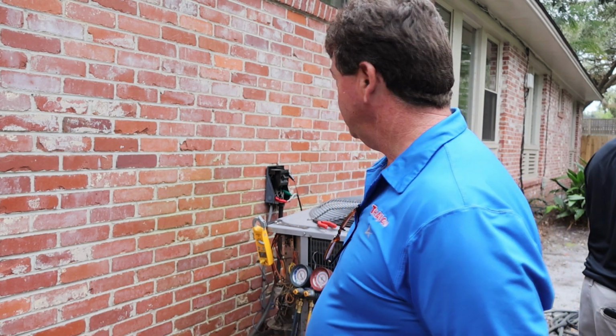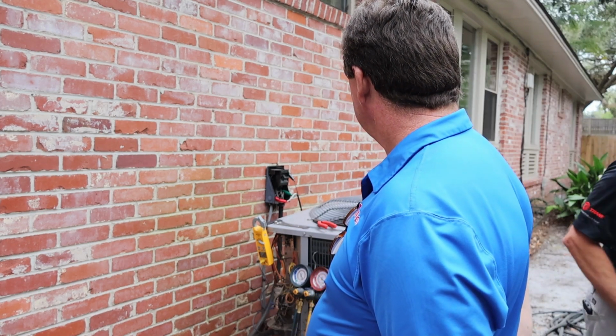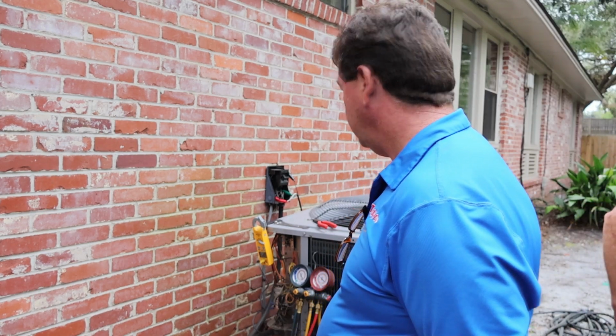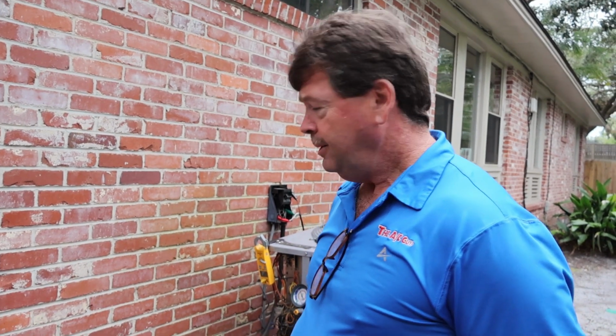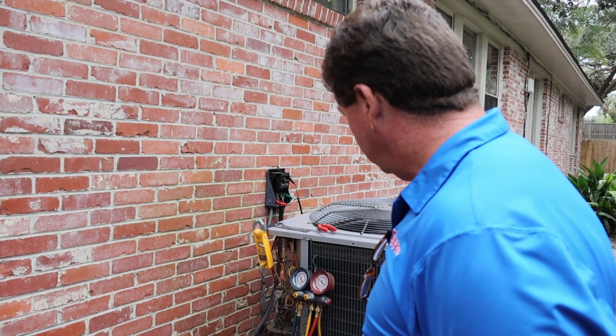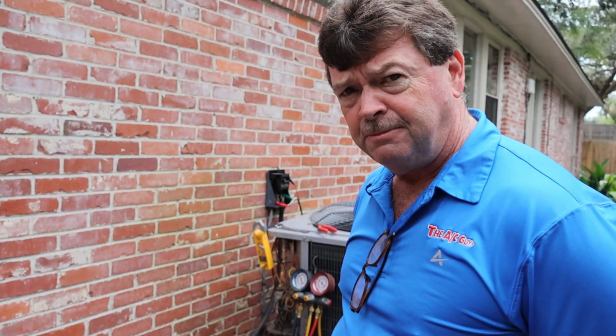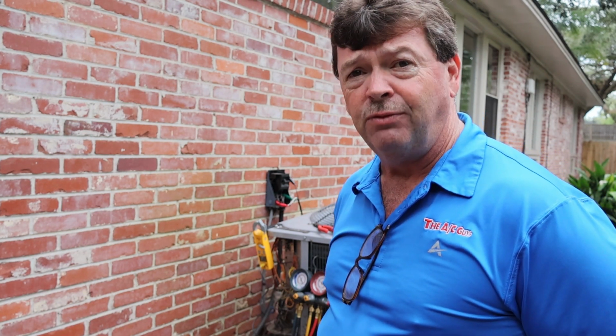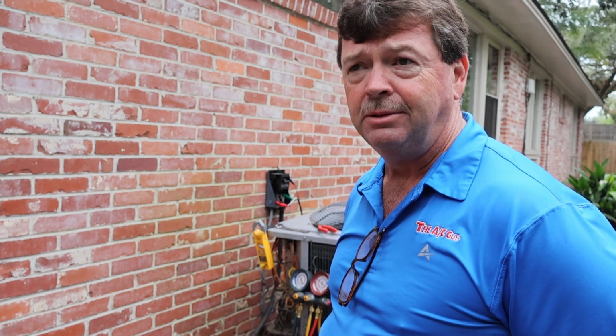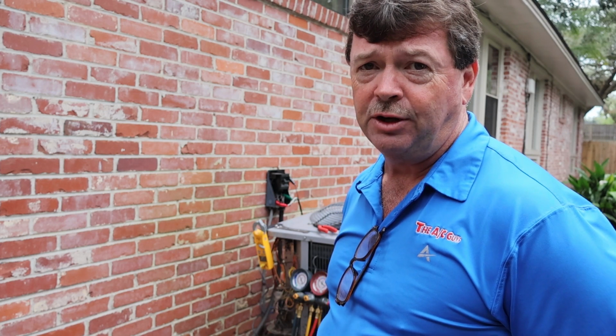We're running a 10 degrees subcooling, and our superheat is what, Dave? 6 degrees. 6 degrees superheat, so Freon charge is probably good. It could stand to be a little higher, but today is a little cool to check cooling charge, so I feel like our Freon's okay. And our coil was pretty clean, so we opted not to clean it first, just because it takes so long for it to dry. Hard to determine Freon pressures with a wet coil.